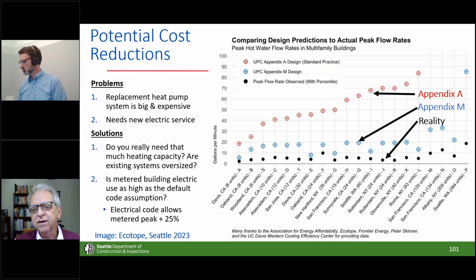But those black dots at the bottom are the actual peak flow rates measured over the course of a year for any of those buildings. So with the traditional system you've been using to design water heating for multifamily, you've been oversizing by 10 or 12 times what the peak will ever be for your building. And with this new Appendix M, you're only oversizing by 2, 3, or 4 times what it will ever be at the peak.